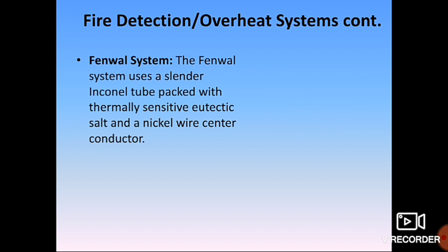Fenwal system. The Fenwal system uses a slender inconel tube packed with thermally sensitive eutectic salt and a nickel wire center conductor. The lengths of these sensing elements are connected in series to the control unit. The elements may be of equal or varying length and of the same or different temperature setting. The control unit, operating directly from the power source, impresses a small voltage on the sensing elements.